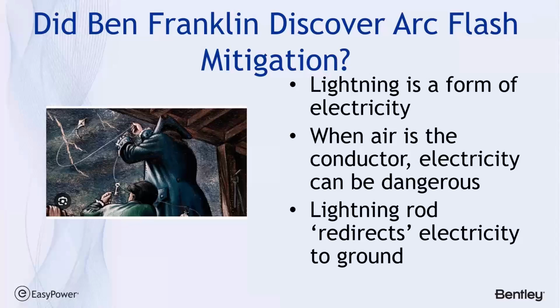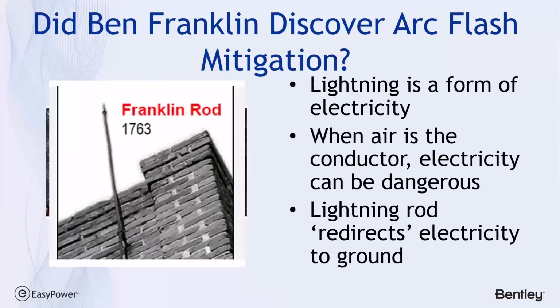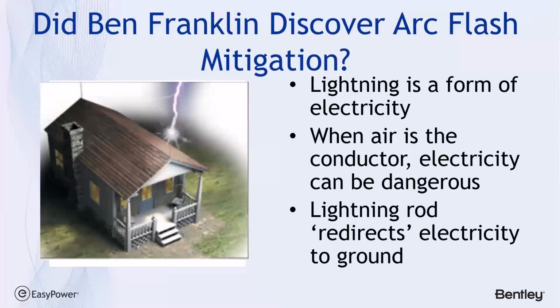Just a thought, my question is, did Ben Franklin discover arc flash mitigation back in the day? Well, he's the guy that's pretty much responsible or credited with defining lightning as a form of electricity, and he recognized that when air is a conductor, electricity can be dangerous. So he invented a lightning rod that redirected the electricity to ground. And the point I'm making is that's similar to what the current technology is, the most recent technology in facility protection, and that's arc quenching, which we'll get into in the mitigation discussions at the end of the series.